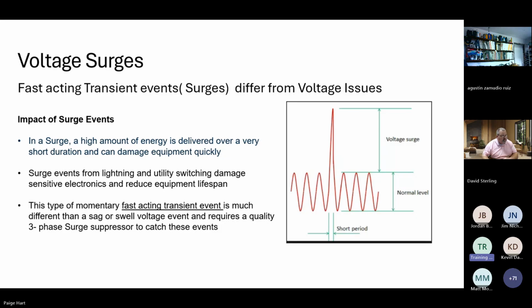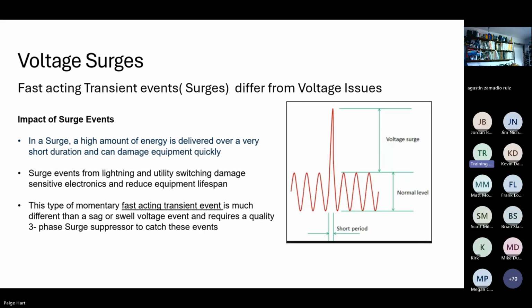You can get surge events caused by lightning in the upper atmosphere. You can get surges caused by utility switching, and by large pieces of equipment turning on and off rapidly in a commercial application. So sensitive electronics can be damaged very quickly, and you can reduce the lifespan of your equipment overall. This type of momentary, fast-acting transient, again, is much different than a sag or swell in voltage, and requires something more than just a voltage monitor. It requires a quality three-phase surge suppressor to catch these events.